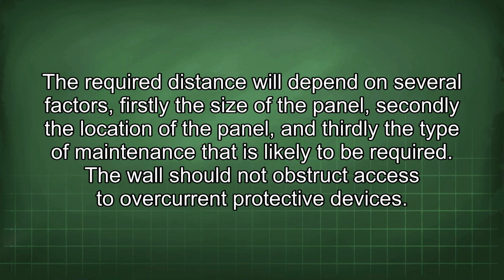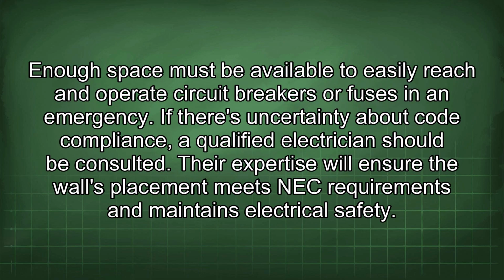The required distance will depend on several factors. Firstly, the size of the panel. Secondly, the location of the panel. And thirdly, the type of maintenance that is likely to be required. The wall should not obstruct access to overcurrent protective devices. Enough space must be available to easily reach and operate circuit breakers or fuses in an emergency.